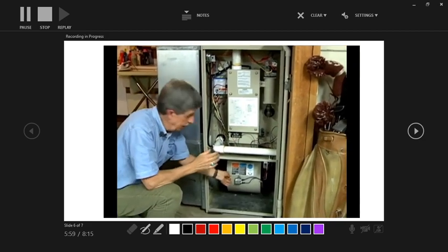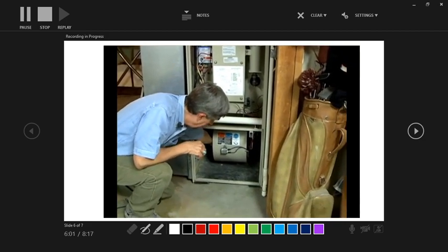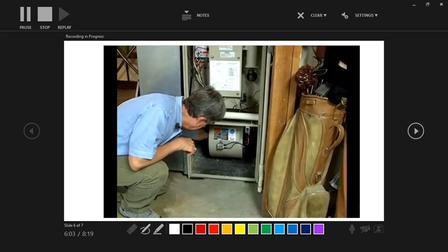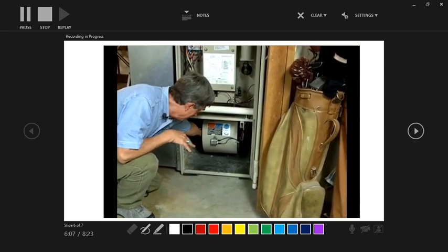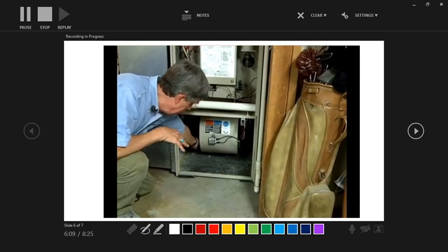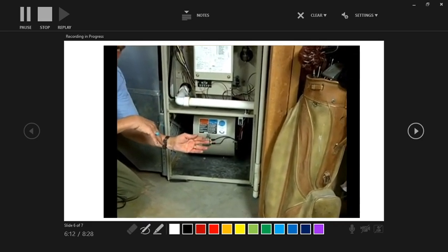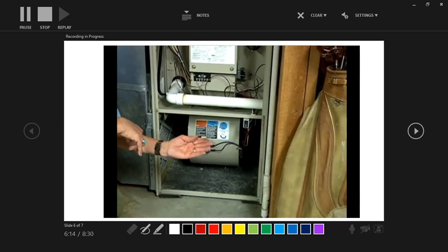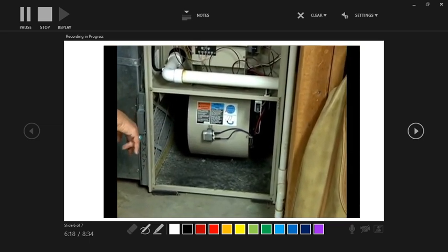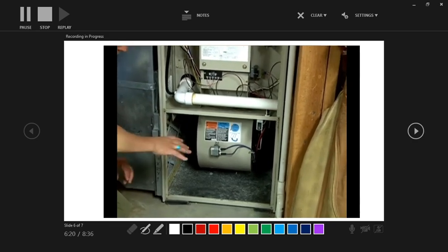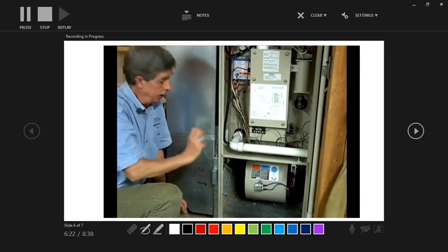Hopefully the fan is clean like this one. You want to make sure that we can check the fins of the fan. Turn the furnace off, of course, cut the power to it, when you do this. And you can get a little bit of dust off of this fan, but this fan's been in about 15 years. That's normal for this kind of time span. So this has been kept fairly clean, so we can probably assume that the coil's pretty clean.